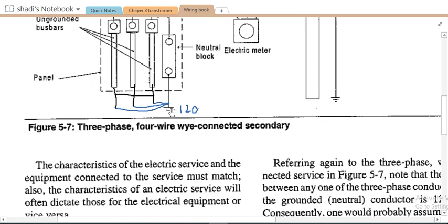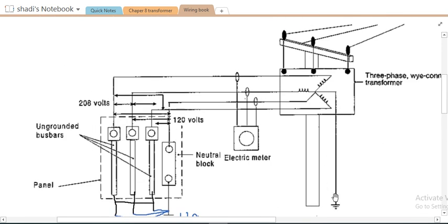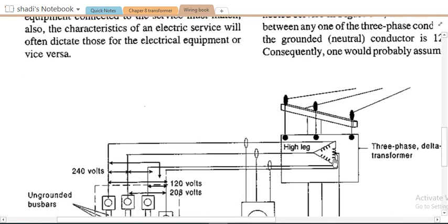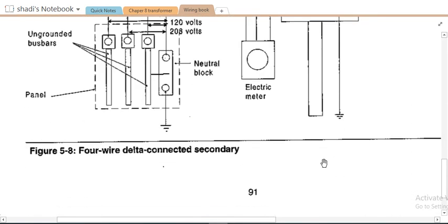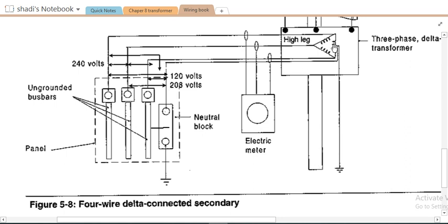Same thing here, by the way, we have the grounding system, which is totally different than the neutral, the grounded conductor, and we will explain it later inshallah when we go to the neutral. Now my concern here in this combination, the delta connection, is that we have three levels of voltages. The 240 basically is the voltage between any line to line, 240, 240, 240. All of these lines will have the 240 voltage difference between them.